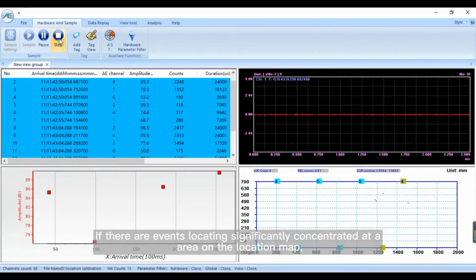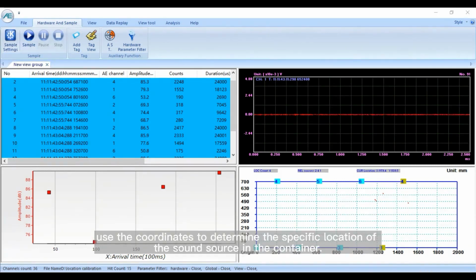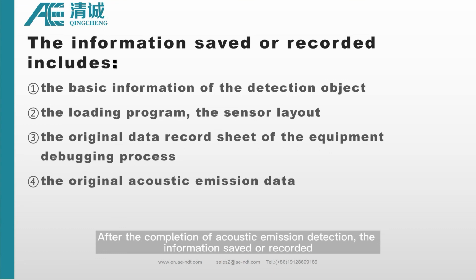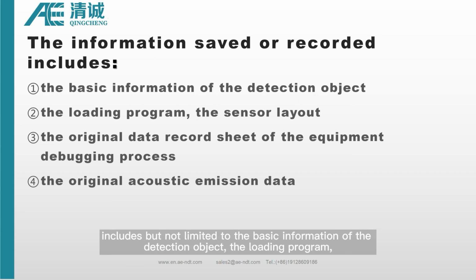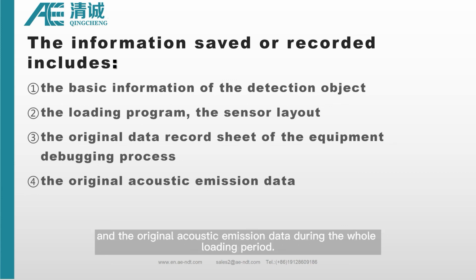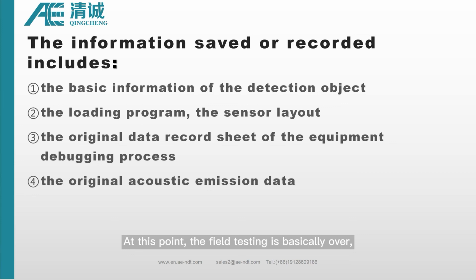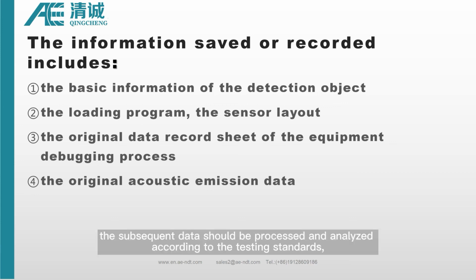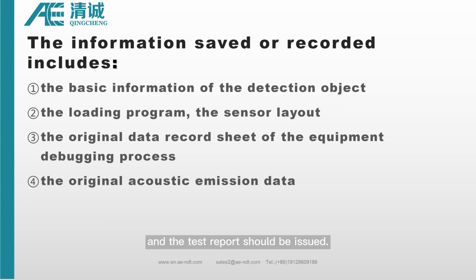If there are events significantly concentrated at an area on the location map, use the coordinates to determine the specific location of the sound source in the container. After the completion of acoustic emission detection, the information saved or recorded includes but is not limited to the basic information of the detection object, the loading program, the sensor layout, the original data record sheet of the equipment debugging process, and the original acoustic emission data during the whole loading period. At this point, the field testing is basically over, and the subsequent data should be processed and analyzed according to the testing standards, and the test report should be issued.